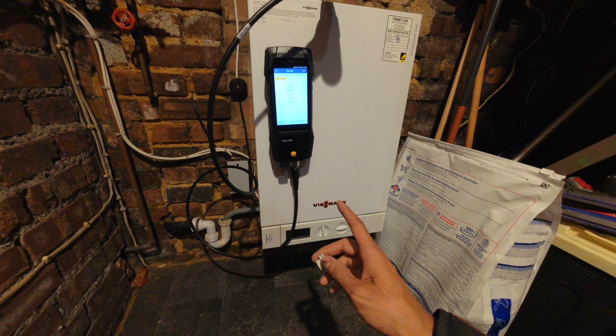Okay, just finishing off with the flue gas analysis. Gas rate was spot on - it's a 35 kilowatt open vent boiler, and it's coming in just under 35 kilowatts, so that's perfect. Maximum rate is only going up to about 70 ppm as well, so I'm happy with that. This one's done, on to the next one.